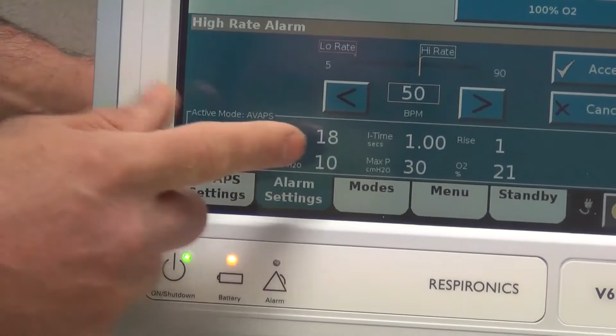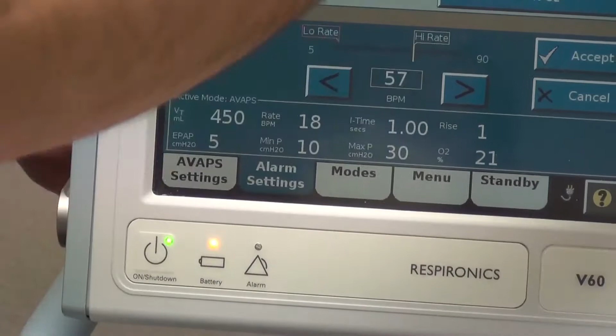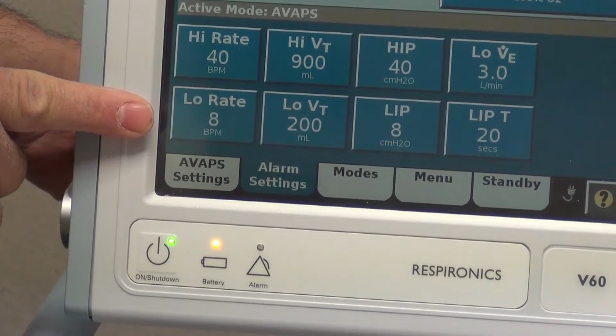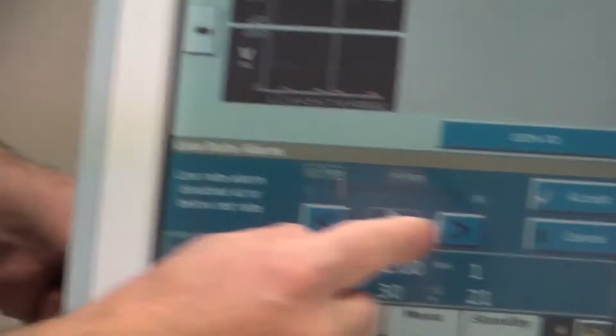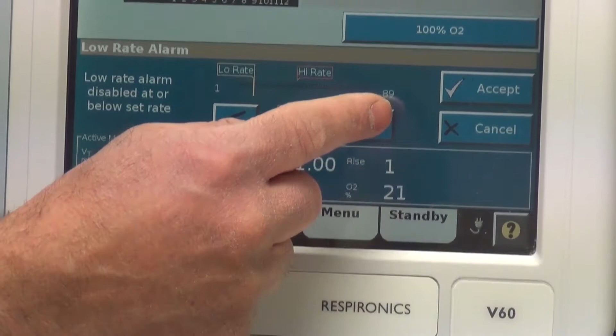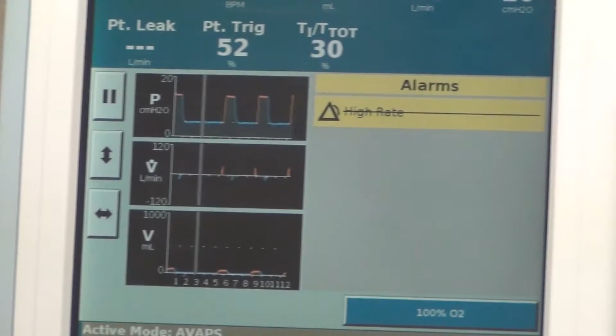We have a high rate. On the other machine we set it to 40, so we're going to set it to 40. If the patient's breathing 40 times a minute, we know that they're really sick or something is going on. So a high rate of 40 is a good number to go with. A low rate, if they breathe less than 8 times a minute, that would be terrible because they wouldn't be moving any air. So maybe we want to do 10 breaths a minute as our minimum. So if they're breathing less than 10 times a minute, the machine will alarm.